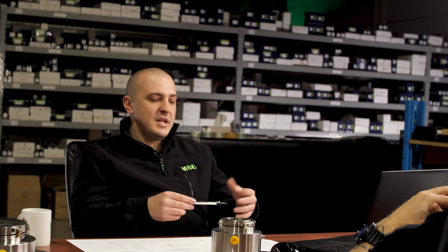Can you tell me about another problem that a customer's brought to you that you've managed to solve? Yeah, sure. This is a double cartridge out of a large mine dewatering pump, a large Sykes pump. Our client kept having pretty serious failures where they were just leaking water everywhere. After pulling apart a few of the old seals, it was pretty clear that the O-rings were heat affected, with severe wear on the faces, and even the faces were exploding. So it became clear to me that the seals were getting way hotter than they should have been.